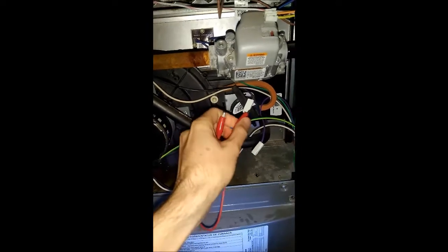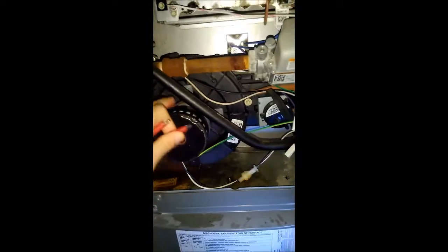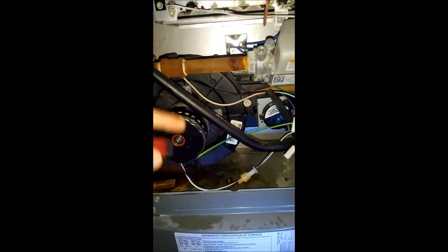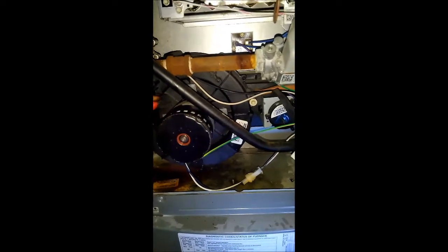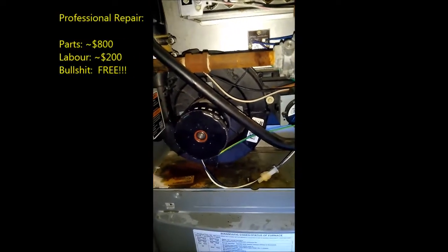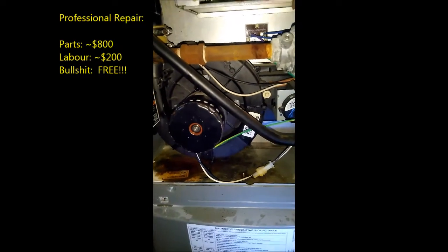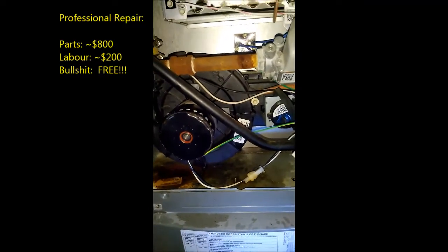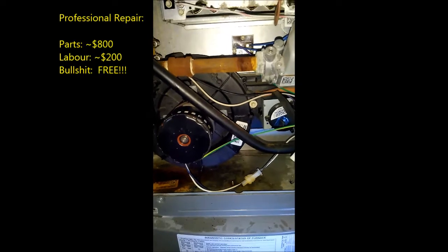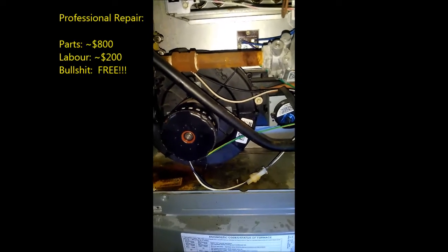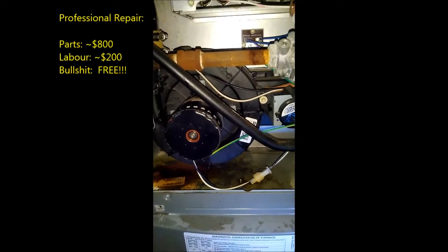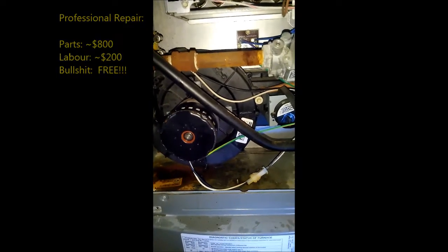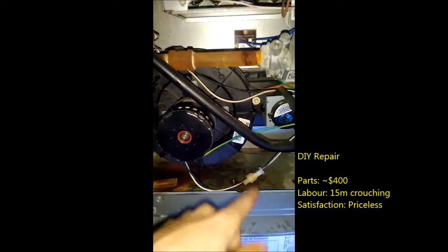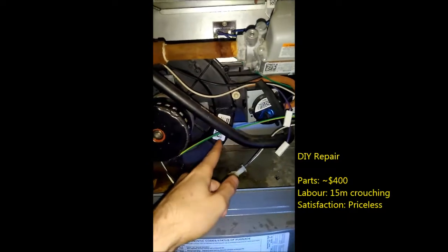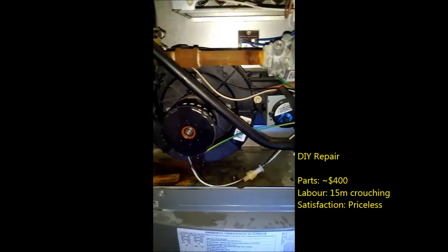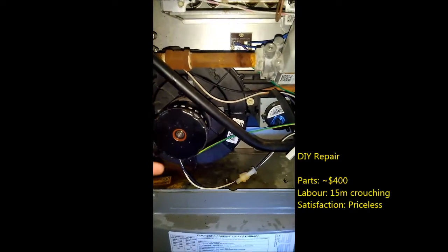It's the inducer assembly, which is, like I said, this motor and this blower here. This is the inducer assembly, motor plus blower. It's just shot to hell. Bearings are gone completely. It grinds when it tries to turn on, just makes a whole bunch of noise. Doesn't spin, doesn't produce any vacuum. It's just completely trash. So you have to buy a new one of those. And the part number you can pull off of this sticker here and just look it up on the internet and buy a replacement unit.